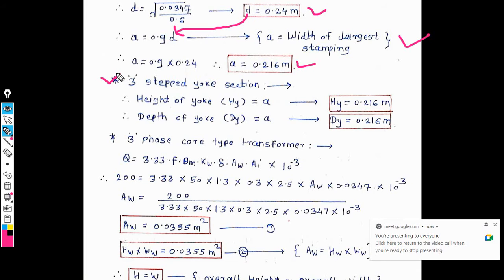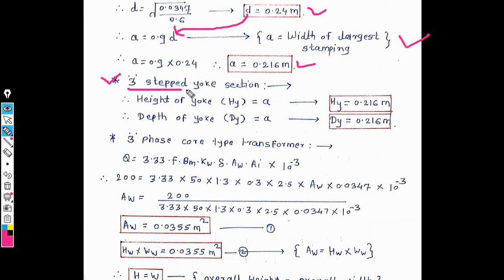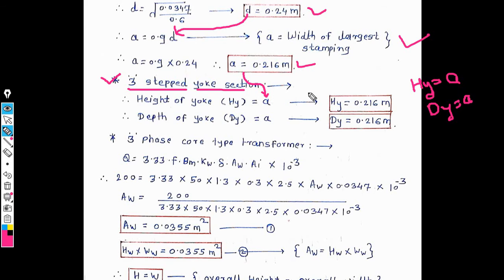For the three-step yoke section, the important formulas are: height of yoke Hy = a, and depth of yoke Dy = a. Since a = 0.216 m, we have Hy = 0.216 m and Dy = 0.216 m. These are the calculated values for the yoke dimensions based on the three-step yoke section concept.